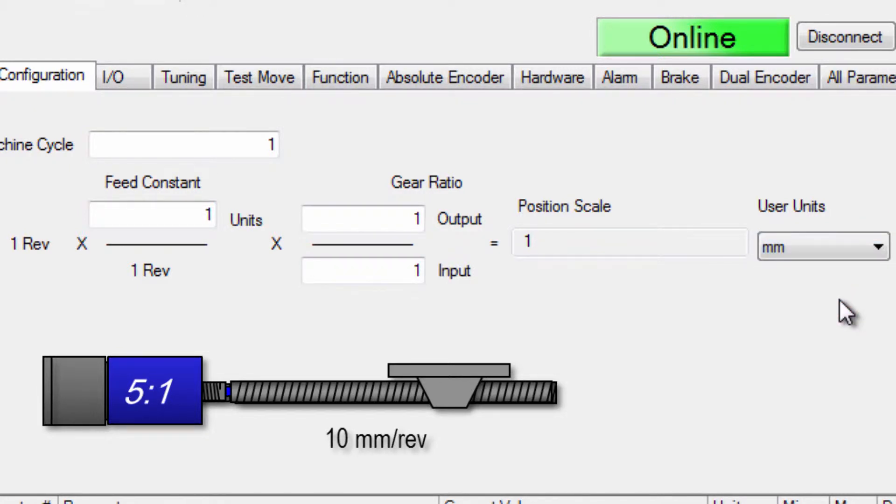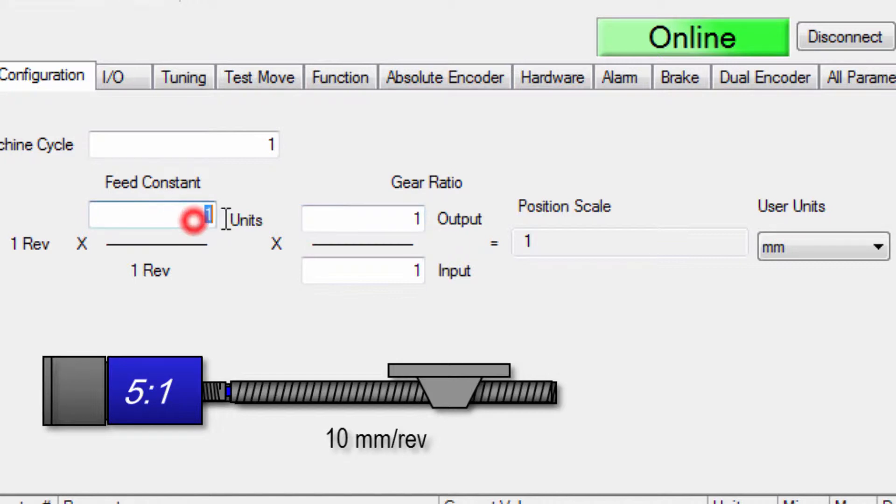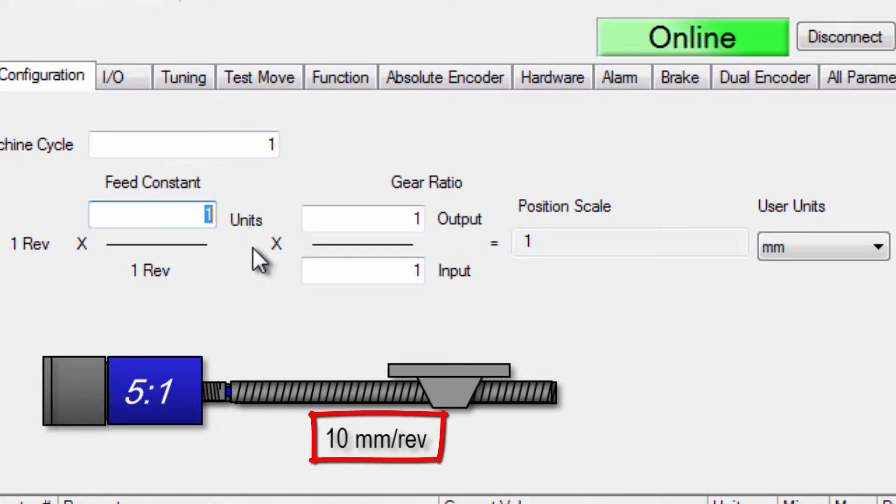Unit selection does not affect the controller operation but it is available for reference and display within the software. Now under feed constant the equation indicates that we need to enter the units moved per load shaft revolution and this screw was 10 millimeters per revolution. So enter 10.